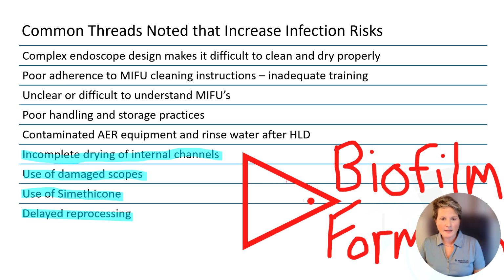And then delayed reprocessing. That's another very important thing that's getting a lot of press lately. Ideally, we have this golden hour. The scope should be taken from the procedure room to the manual cleaning sink, and ideally to the high-level disinfector machine, within 1 hour of exiting the patient. Anything beyond that is considered delayed reprocessing, and there are additional instructions, basically soaking instructions, that you need to follow according to the manufacturer's instructions.